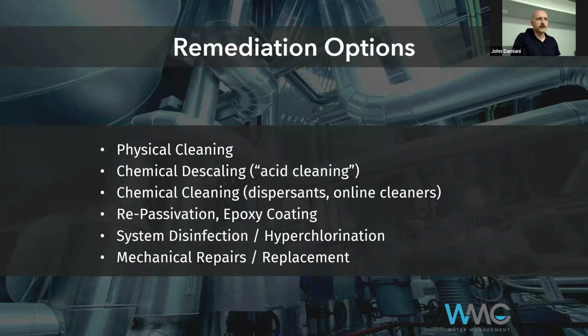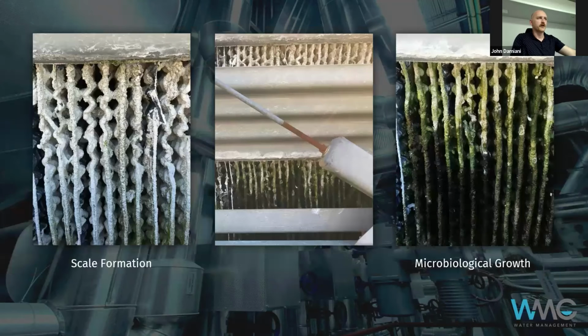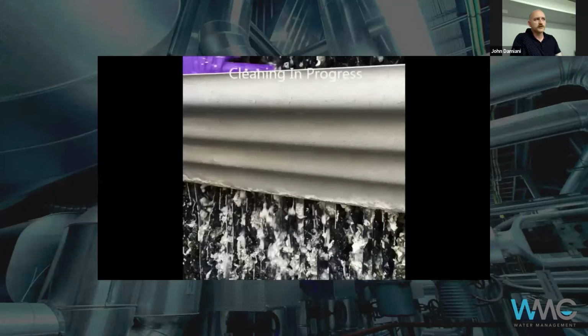So there are options for remediating things. Ideally, if we get the water treatment correct, we don't have to go to these measures. But just to give you an idea what that looks like, here's a tower that had pretty severe scale and biofilm. Like I said, it often goes hand in hand, because if the treatment's neglected, you usually have problems with both. But here's a product we use which is an online cleaner.